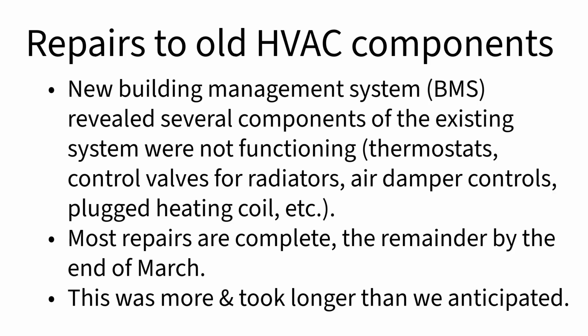Additionally, we found one heating coil that, due to low flow over the years, had plugged sometime in the past. So we had to unplug that heating coil. We also had to replace maybe half a dozen thermostats, half a dozen radiator control valves, and some air damper controls.